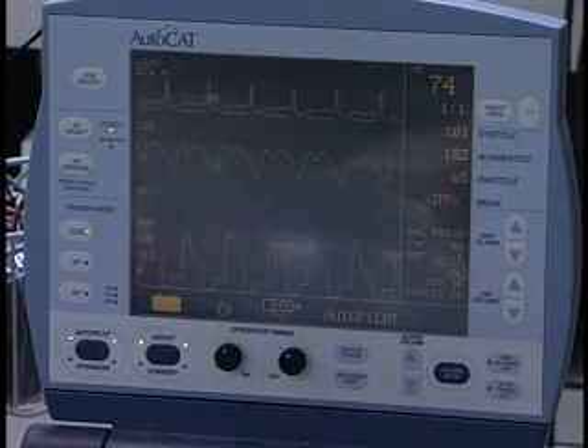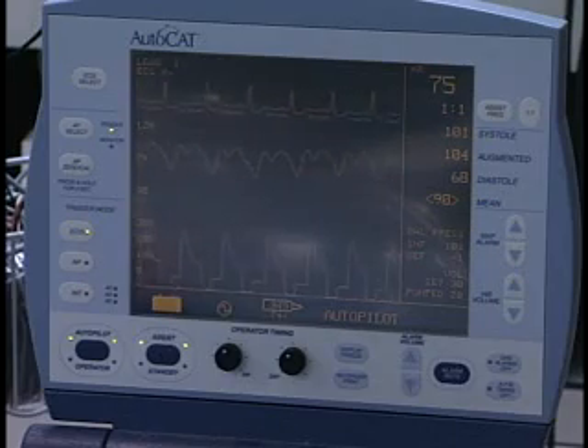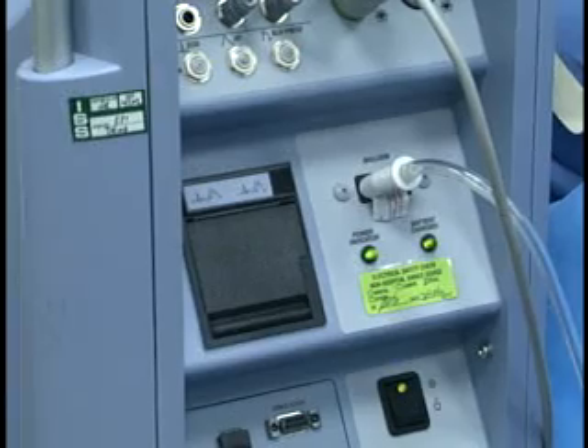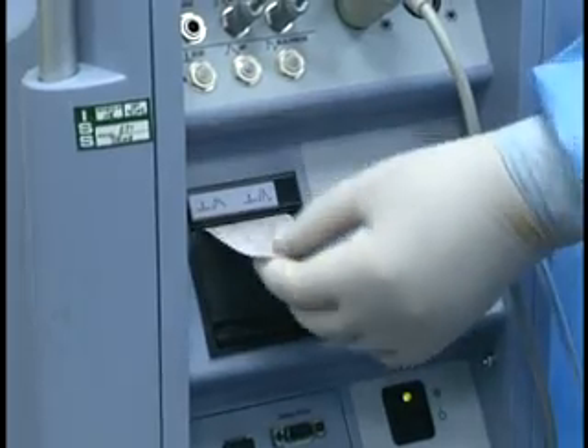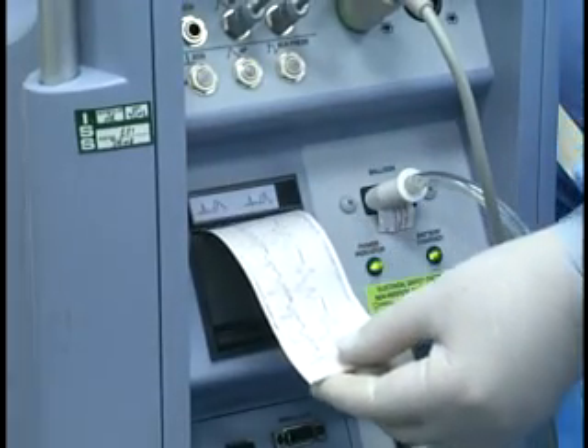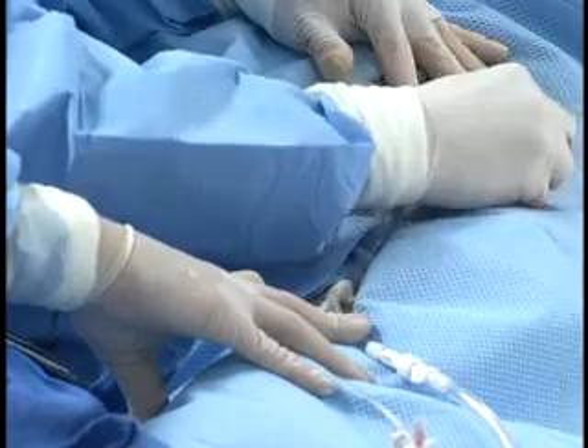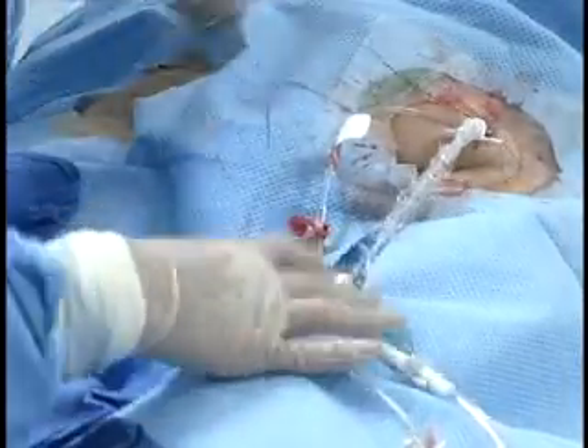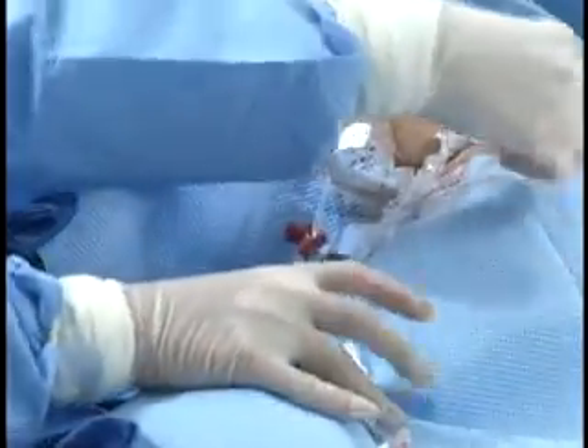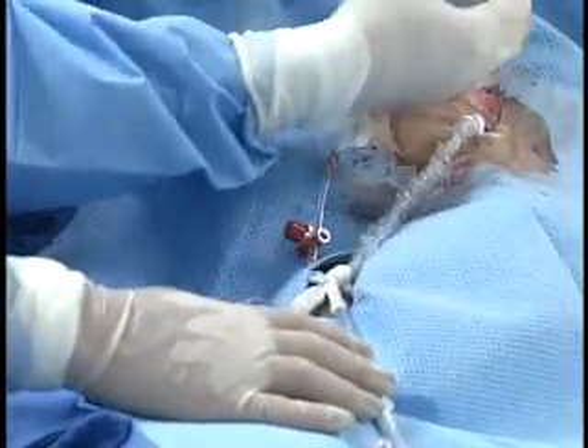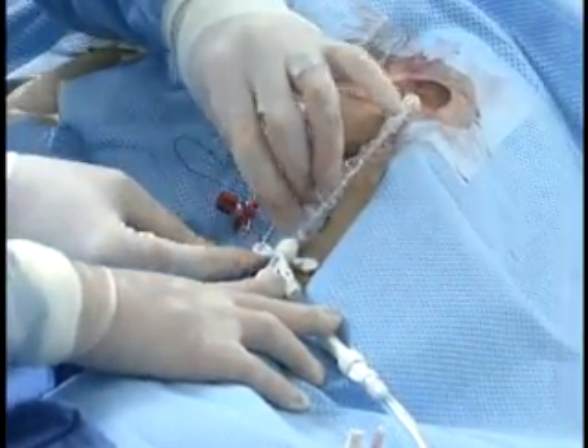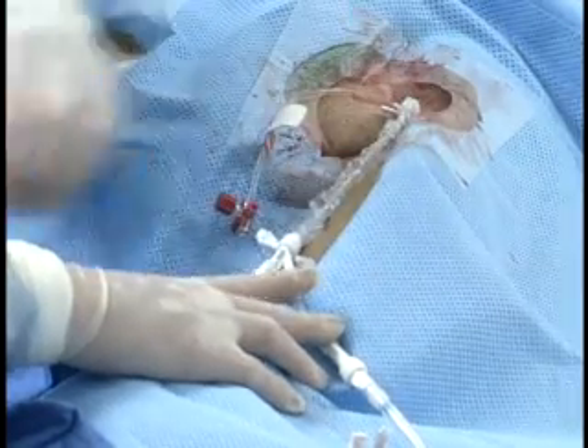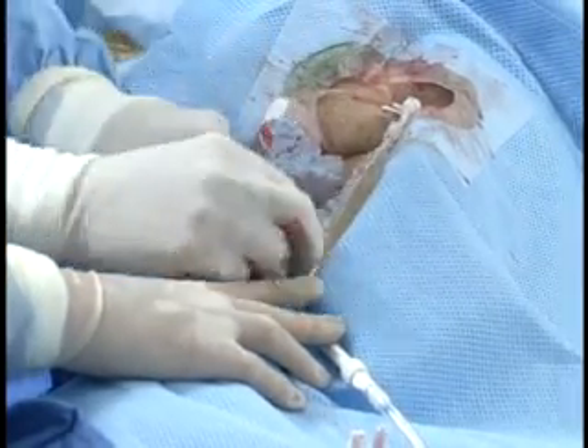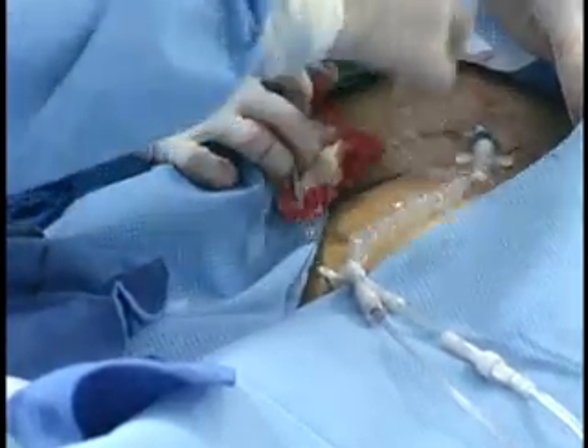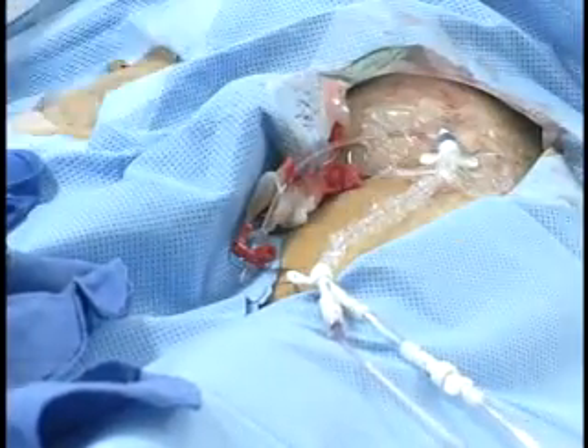Observe the balloon pressure waveform for its normal morphology, indicating a properly functioning balloon and proper sizing. Verify timing by obtaining a strip chart recording of the arterial pressure waveform. Secure catheter to the skin at the hemostasis cuff and at the catheter bifurcation to reduce the risk of catheter migration. Use only the wingtips designed for sutures. Avoid anchor sutures around the catheter body. Apply a sterile dressing to the insertion site, as described by hospital policy.